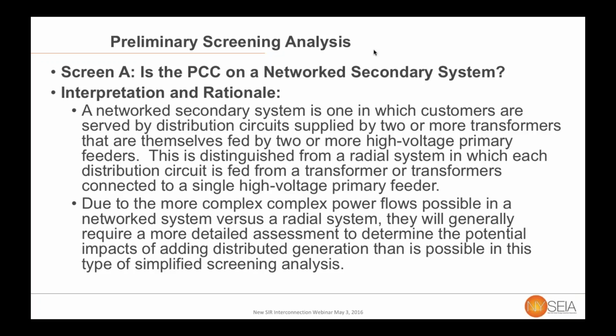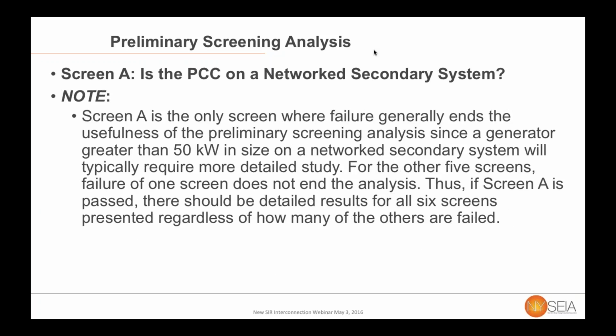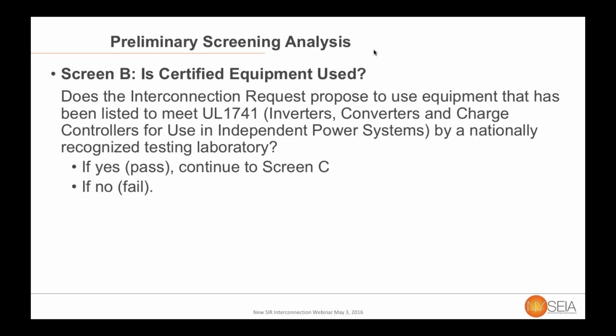Generally in a networked system, they are more complex, and therefore for systems over 50 kilowatts, we really do need additional study. So screen A is sort of unique amongst the screens in that if you fail screen A, it really does eliminate much value in all the other screens. And so generally failure of this means that you're likely to need to go to a detailed study for most network systems. And so this is one of the few screens. If you pass screen A, the utilities will continue on through the rest of the screening methodologies. And so even if you failed screens B or C, you'll still get results for all of them. Because as Melissa mentioned, maybe there are small tweaks, maybe there are things that you can do to address those failures, and you really do want to see how the whole screening analysis works for those systems that are on radial feeder lines.